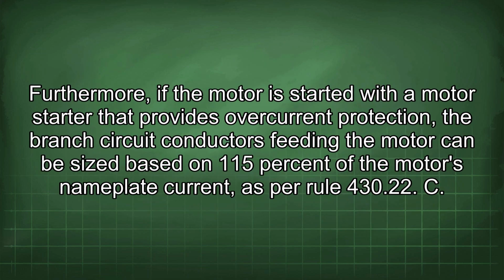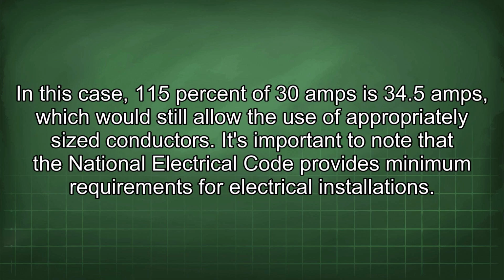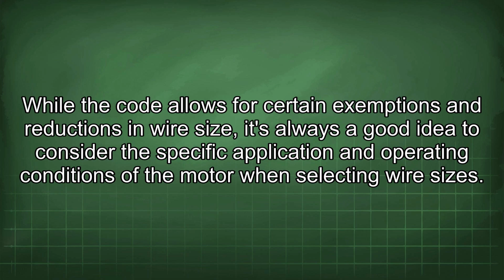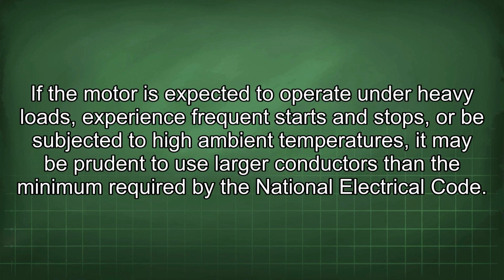Furthermore, if the motor is started with a motor starter that provides overcurrent protection, the branch circuit conductors feeding the motor can be sized based on 115% of the motor's nameplate current, as per Rule 430.22 C. In this case, 115% of 30 amps is 34.5 amps, which would still allow the use of appropriately sized conductors. It's important to note that the National Electrical Code provides minimum requirements for electrical installations. While the code allows for certain exemptions and reductions in wire size, it's always a good idea to consider the specific application and operating conditions of the motor when selecting wire sizes. If the motor is expected to operate under heavy loads, experience frequent starts and stops, or be subjected to high ambient temperatures, it may be prudent to use larger conductors than the minimum required by the National Electrical Code.